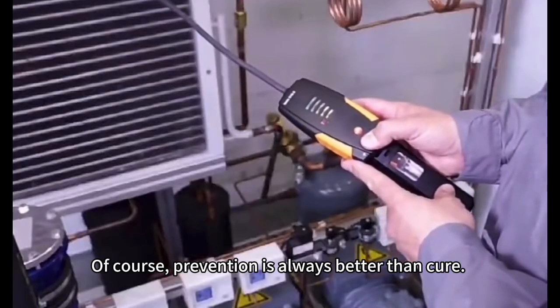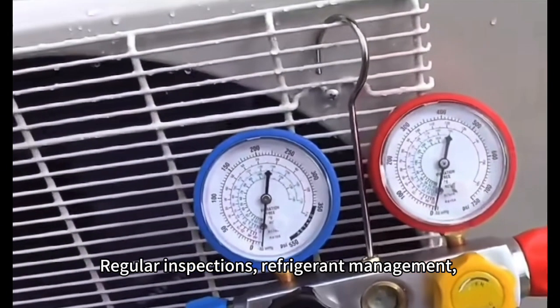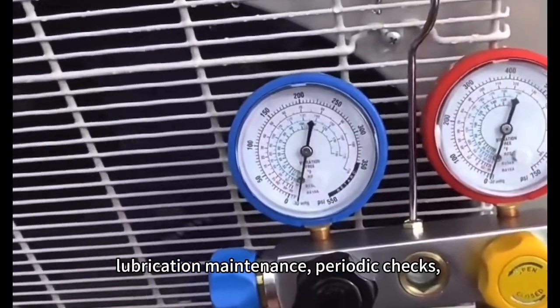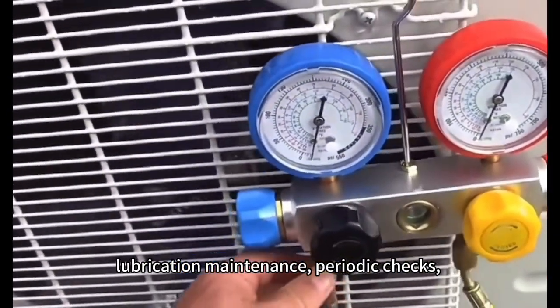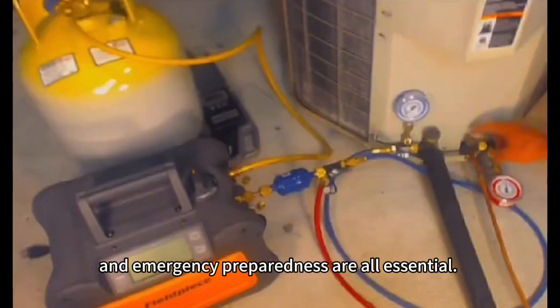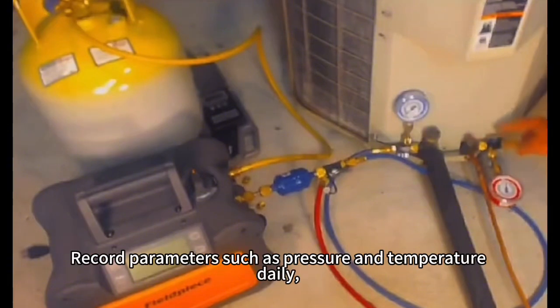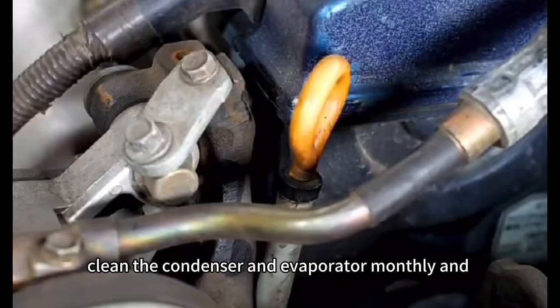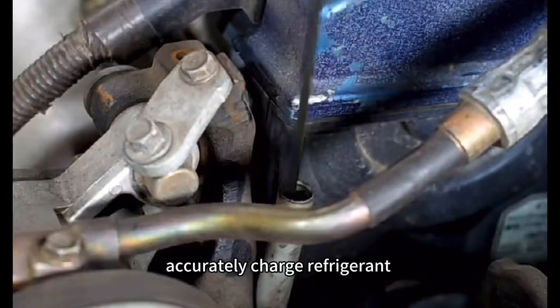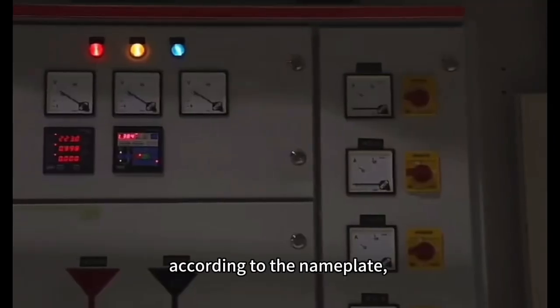Of course, prevention is always better than cure. Regular inspections, refrigerant management, lubrication maintenance, periodic checks, and emergency preparedness are all essential. Record parameters such as pressure and temperature daily. Clean the condenser and evaporator monthly and accurately charge refrigerant according to the nameplate.